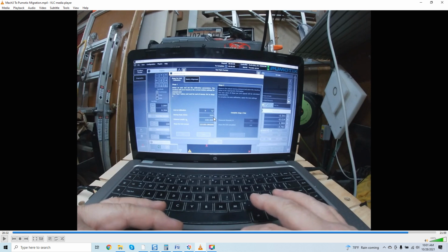Well, now you've streamlined the process because you first have to program in the software the speed at which it's going to perform the calibration after selecting your axis. And then you will keep increasing this speed independently on that particular axis until you find that steps are missed or, again, we lose accuracy. If we're not going to have that level of consistency, and that's the key word here, I recommend at least 5 actual measurements, minimum of 5. My precision guys do 10 to 15 per axis, and what they're looking for is that consistent level of repeatability. Once you find that, you're golden.